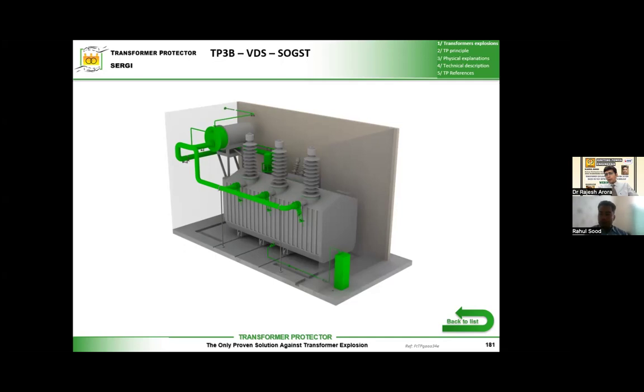Okay, now before I invite questions, last question from my side. In all nitrogen injection systems of any make, parallel to that, there is some connection going to my relays so that I can isolate my system. But in your presentation, I couldn't see any control system that is giving a command to any relay inside the control room so that my system can be isolated during a problem in the transformer.